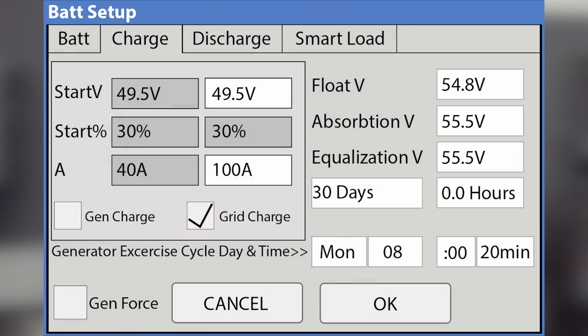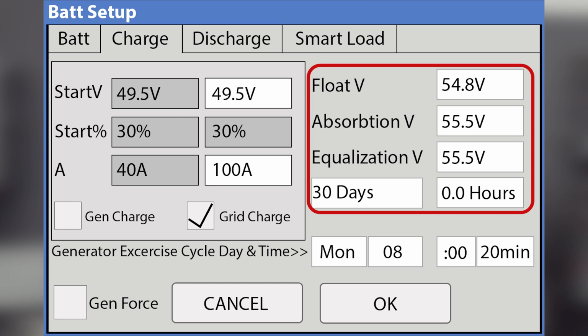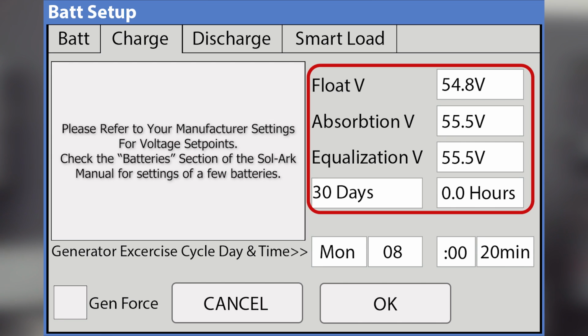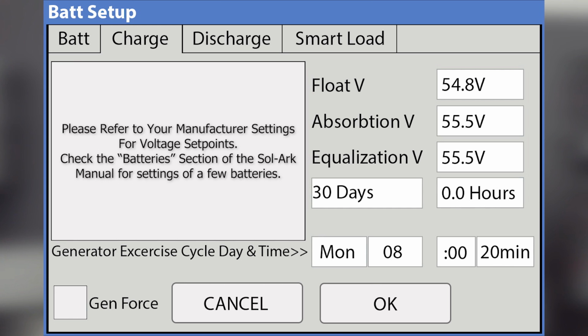And this is also a very important section on the right hand side of this screen. You have your float, absorb, equalize, equalize hours and voltage, and days. So these are going to be settings that you're going to get from the spec sheet of whatever battery you're using. So go ahead and just use your manufacturer recommended settings here. We do have a lot of the common brands in the Sol-Ark manual, but we recommend that you go to your actual manufacturer's website, get their spec sheet, and program it accordingly.